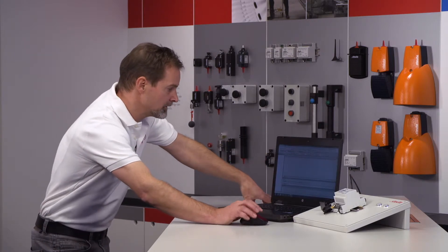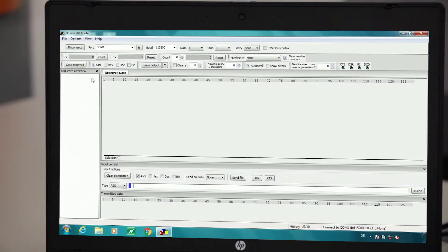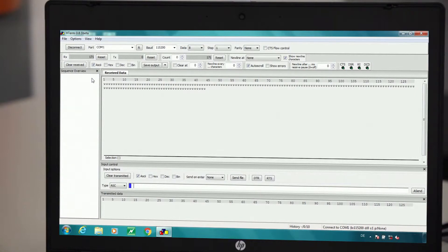At the top we can see a COM port, and this COM port must be selected in order to activate communication. In this case the setting is COM port 1, but this can vary from system to system. When the appropriate COM port has been selected, we then press Connect, which means that the connection to the RS-232 interface is cleared for use. We can see this has worked because the incoming signals are now visualized one after the other.